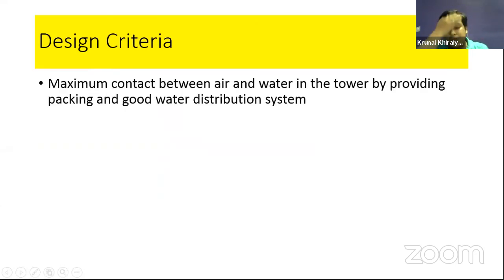So the first and very important criterion is that the maximum amount of contact should happen between the air and water. It takes time, and with the help of time and the contact area, the interfacial area, you get a larger amount of heat transfer, and you get a lower cooling water temperature. For that, you need to provide the packing and a good water distribution system that is required for maximum contact between the air and water. This is the most important criterion.